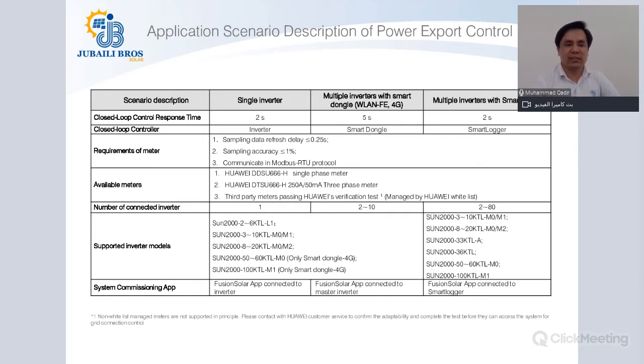For that, in the case of a single inverter, you will choose the inverter as the closed loop controller. In the case of multiple inverters with the dongle, you can have the smart dongle as the closed loop controller. In the case of multiple inverters with a smart logger, the closed loop controller will be the smart logger. Since you will also need a power meter, you will use either a smart power sensor from Huawei or a third-party power meter. Such power meters are listed in the smart dongle or smart logger manual, which can also be sent out from our side, and we can give you this power meter list, which you can source through third parties as well, to do the zero export control or the type of control that you require.